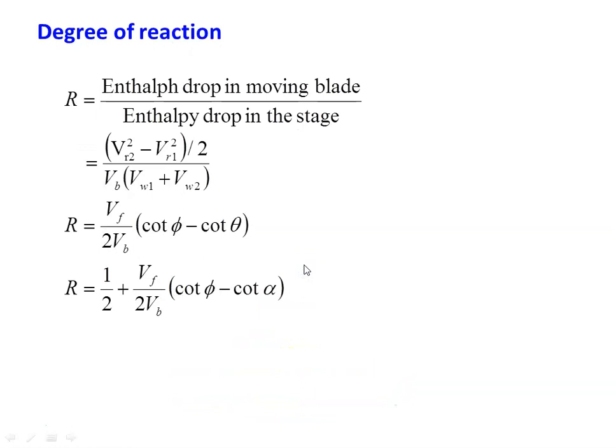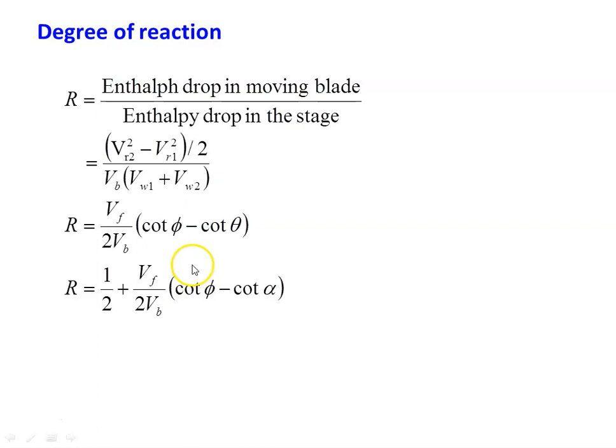One important parameter in the reaction turbine is the degree of reaction. The degree of reaction R is defined as the enthalpy drop in the moving blade divided by the enthalpy drop in the entire stage. The enthalpy drop in the moving blade equals (vr2² − vr1²) / 2, due to the change in pressure across the moving blade. The enthalpy drop in the stage equals the work produced: vb × (vw1 + vw2). Substituting from the velocity triangle: R = (vf / 2vb) × (cot φ − cot θ), or equivalently R = 1/2 + (vf / 2vb) × (cot φ − cot α). The degree of reaction varies from 0 to 1.